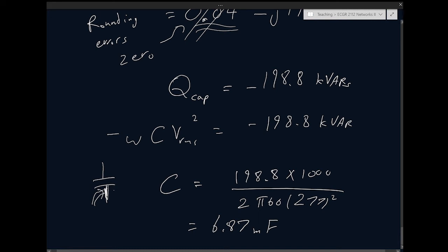So I think they did the calculation and they found out that with a certain cost of capacitors, it turns out you can pay off the caps by reduced demand charge in 12 months. And after 12 months, you're free. I mean, the caps pay for themselves within 12 months. Okay? That's why it's very economically attractive for institutions to install caps and improve their power factor.